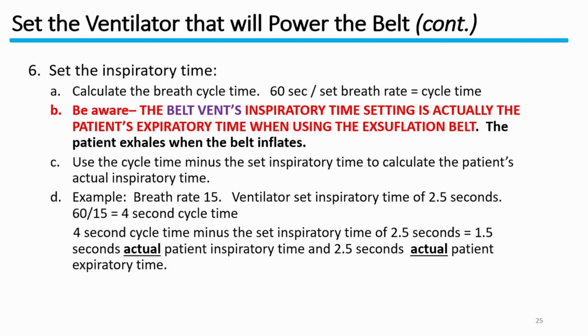Calculate the breath cycle time. 60 seconds divided by the set breath rate equals the cycle time. Be aware, the belt vent's inspiratory time setting is actually the patient's expiratory time when using the exsufflation belt. The patient exhales when the belt inflates. Use the cycle time minus the set inspiratory time to calculate the patient's actual inspiratory time.